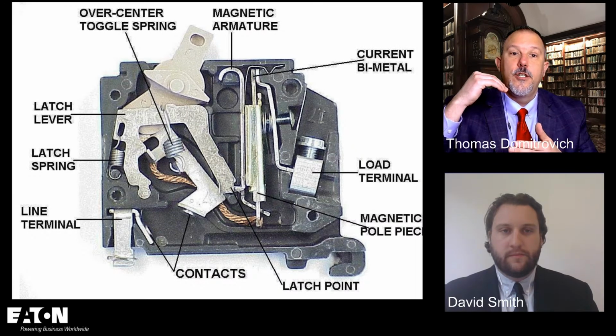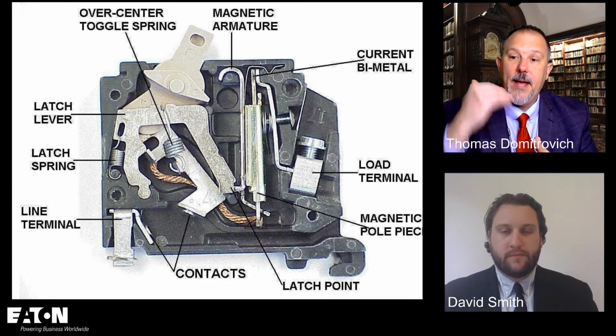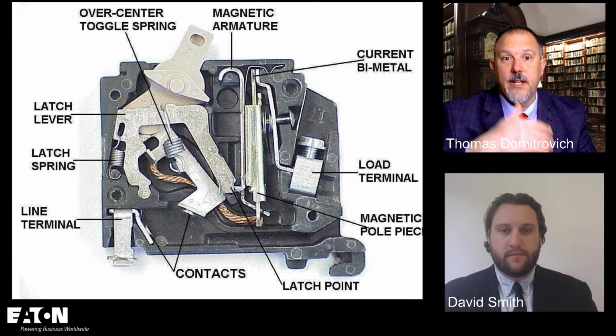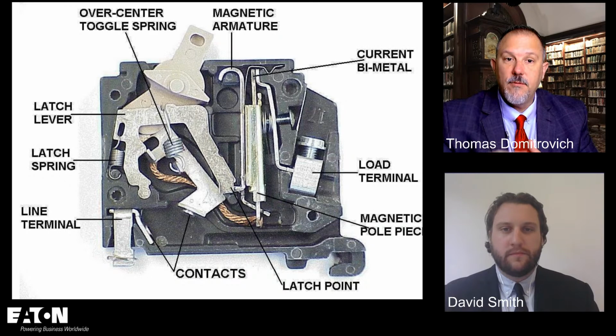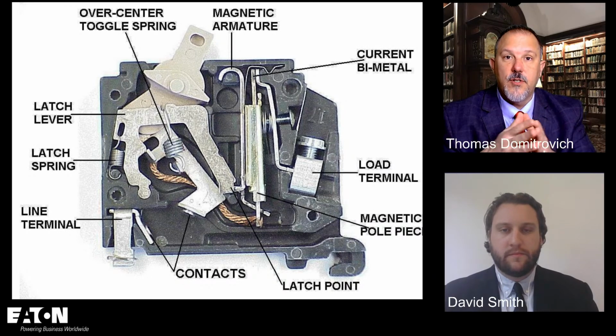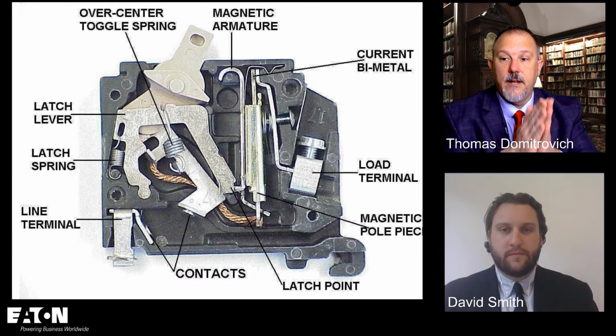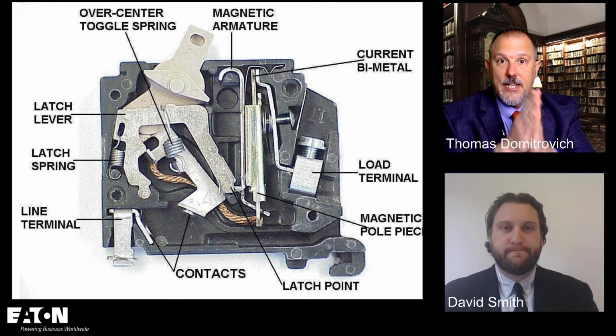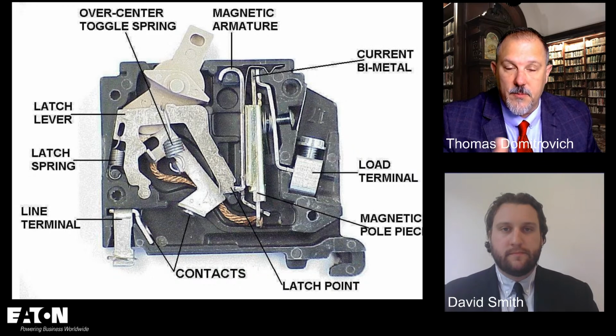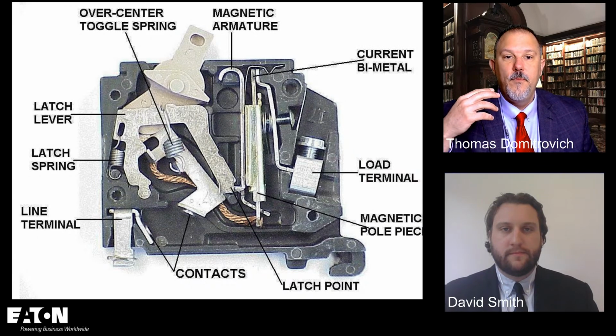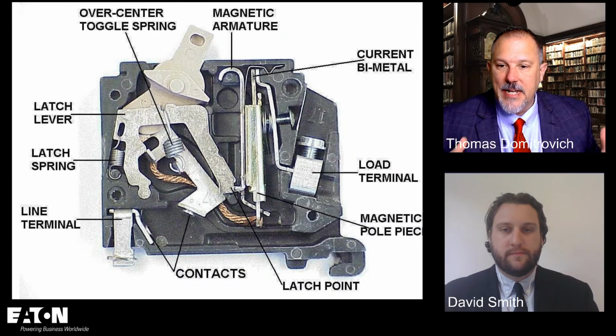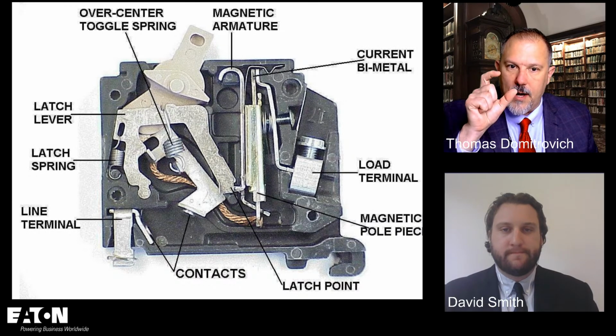And to determine, from an ampacity perspective, from a protection standpoint like 20 amps, the amount of material that we have, our scientists will sit down and tell you what the composition of the metals should be so that it bends when we need it to bend based upon that current. But it's a very mechanical device, to your point. So the trip curves for this are very wide.